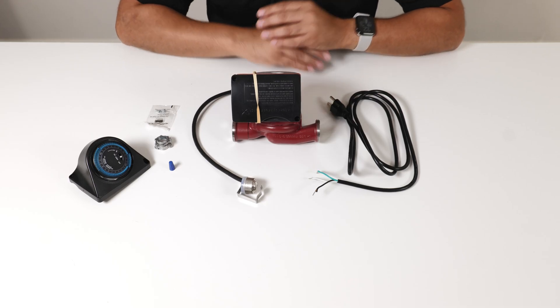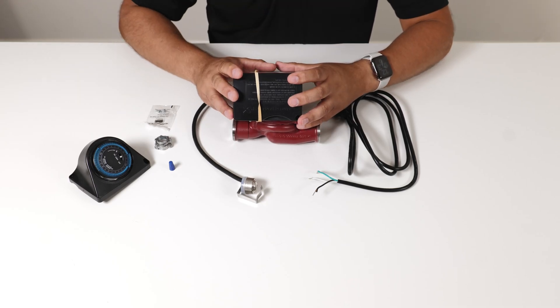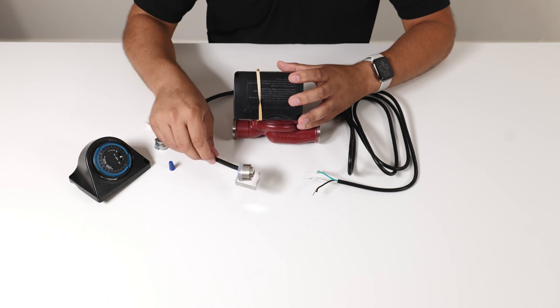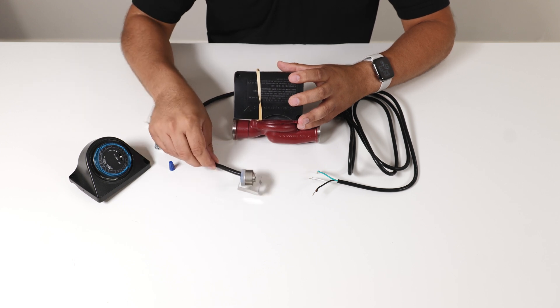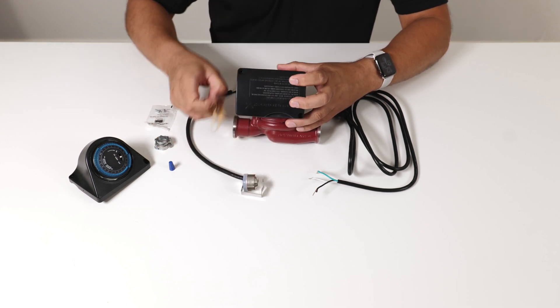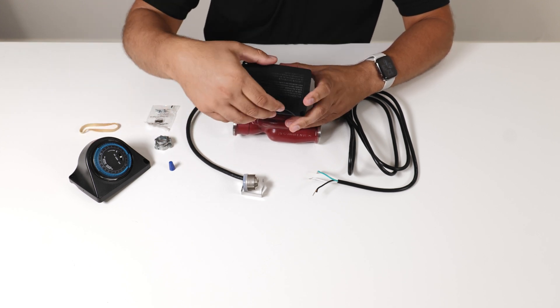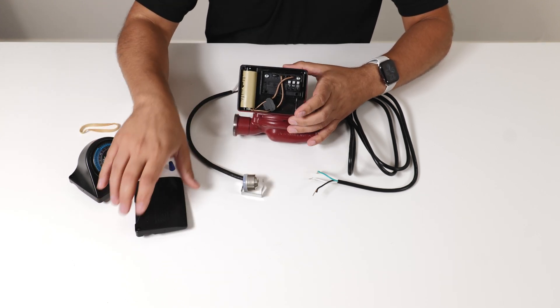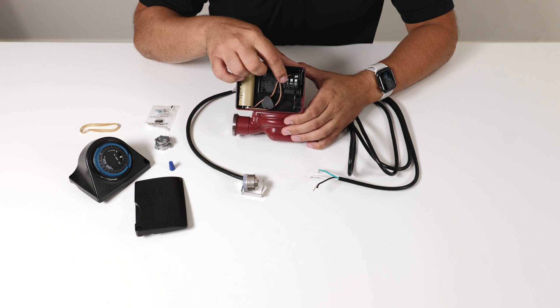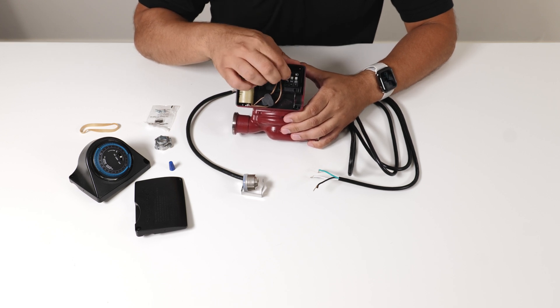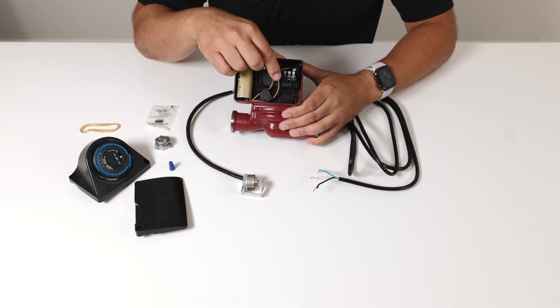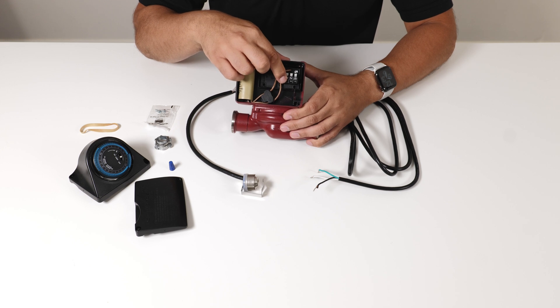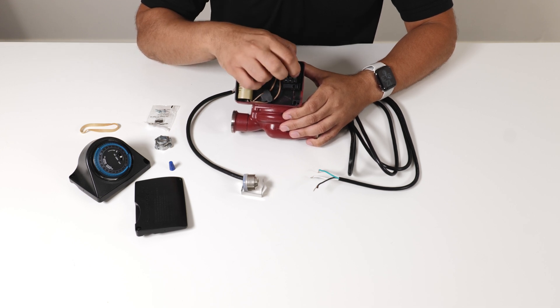Alright so here we have the UP15 type circulator from Grundfos and we're going to wire this Aquastat to it. We're going to remove this rubber band and open up the terminal box. Now the first thing you see are three connectors here. These are pin type, you push to open. You have your line coming in, your neutral and your ground.